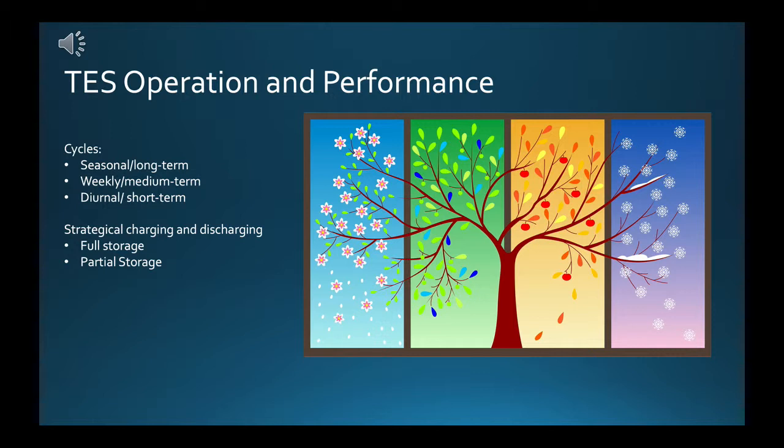For seasonal long-term storage, TES operates on annual or seasonal cycles and usually takes advantage of seasonal climatic variations. Seasonal TES systems have a much greater capacity than daily TES, often by two orders of magnitude. Thermal losses are more significant for long-term storage, so more effort is made to prevent thermal losses in seasonal rather than daily TES. While diurnal systems can generally be installed within a building, seasonal storage requires such large storage volumes that separate locations are often required.